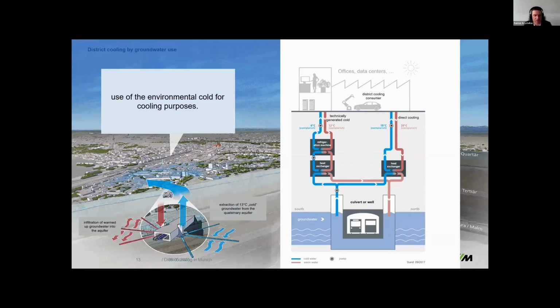Here you can see it. Underneath the surface, around 10 meters, there's the groundwater. It has around 11 to 13 degrees, and we try to use it. In one way, we extract the groundwater with a culvert or well and transport it in pipes to the buildings where we use a heat exchanger for direct cooling, or if necessary, we use chillers, for example, if the customer needs 6 degrees. A well is known, but a culvert, I will show you later what that exactly is, but it has something to do with the subway here in Munich.